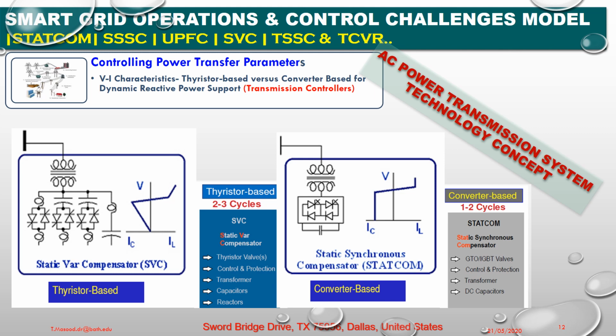Okay, now we are going to discuss V-I characteristic, thyristor based versus converter based for dynamic reactive power compensation. If you can see here, this is my thyristor based SVC, and this is my converter based STATCOM. The first takes 2 to 3 cycles to compensate, and the second takes 1 to 2 cycles. Okay, this is my V and I curve for the SVC, and this is the curve for my STATCOM. Okay, STATCOM is essentially an alternating voltage source providing voltage support behind a coupling reactance with the corresponding V and I. This is my coupling transformer, providing V and I respectively on both sides here.